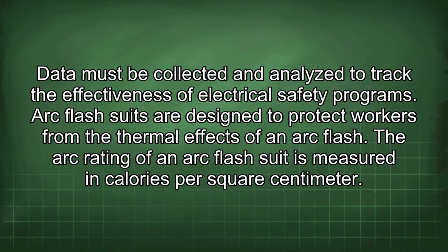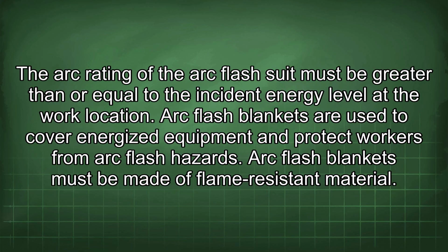Arc flash suits are designed to protect workers from the thermal effects of an arc flash. The arc rating of an arc flash suit is measured in calories per square centimeter. The arc rating of the arc flash suit must be greater than or equal to the incident energy level at the work location. Arc flash blankets are used to cover energized equipment and protect workers from arc flash hazards.